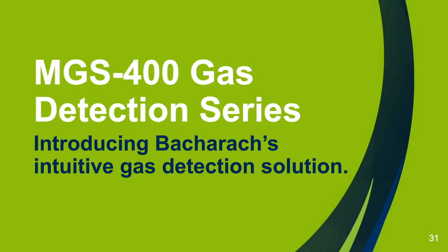So we'll have a look at the MGS-400 gas detection series, which is the new solution from Bacharach, which is really designed around enabling and enhancing and easing the capacity to comply with the refrigerant safety codes out there, such as ASHRAE 15 and EN378, but to do so in a very intuitive way, which takes some of the mystery out of gas detection and essentially enables people to feel that they have a very easy, very straightforward system to set up, use, and configure.